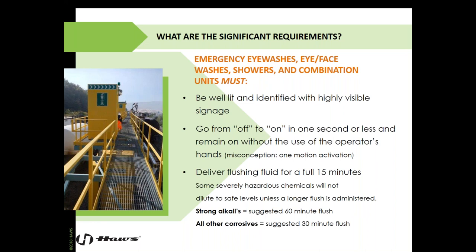Now, the delivery of the flushing fluid has to be for a full 15 minutes. This is a long time, and depending on the chemical that you are exposed to, it can be even longer. So a full 15 minutes is required. That's standard. But as you can see at the bottom of the slide, strong alkalis have a suggested 60-minute flush. That's a long time to remain in emergency first aid equipment, showers, and eye face washes, which makes compliance with this standard even more important because we want to take into consideration victim comfort.